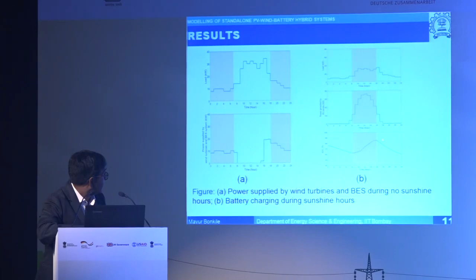In the afternoon, this is the load, and this is the power generated by PV. From the graph, it is clear that PV is generating more power, and this energy we are storing inside the battery. So this SOC is increasing. It means the battery is charging. During the night period, there is a decrease in the state of charge of the battery. The allowable depth of discharge is 60% because we cannot fully drain the battery. So the allowable depth of discharge at the time of design is 60%.